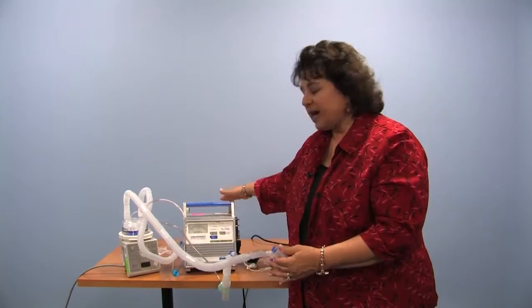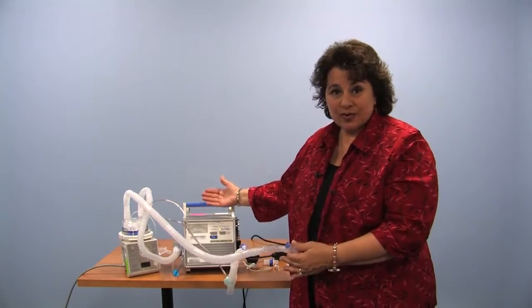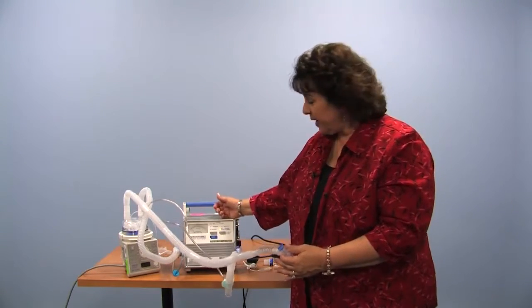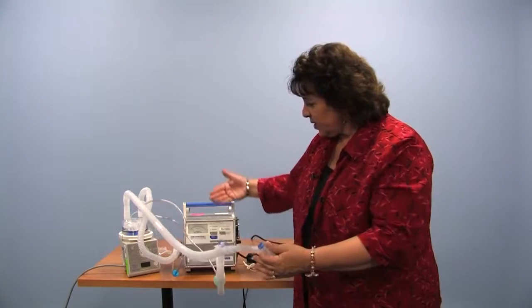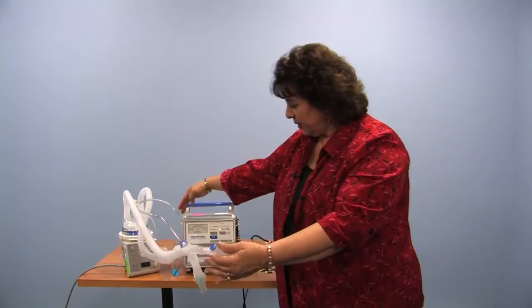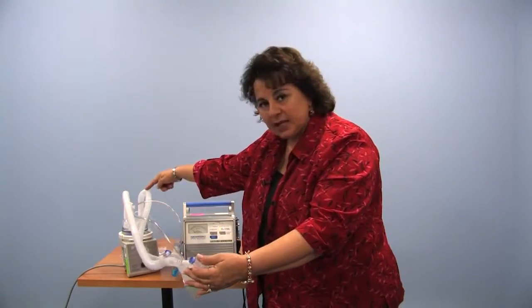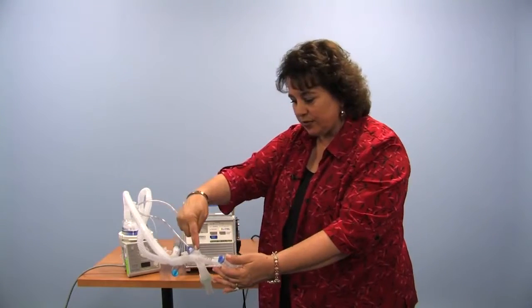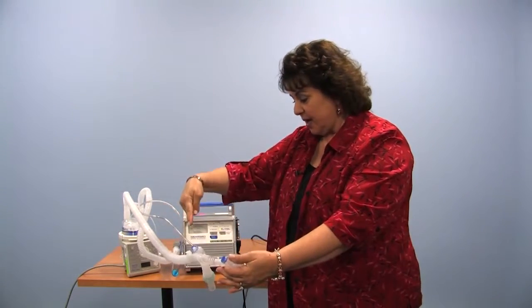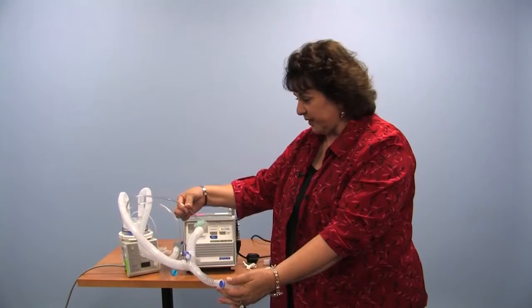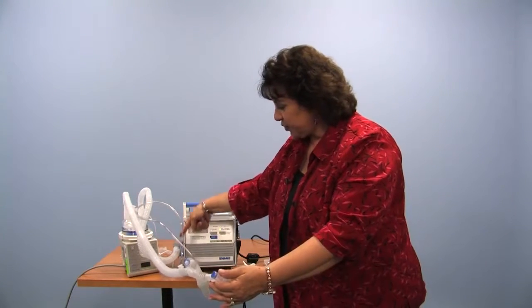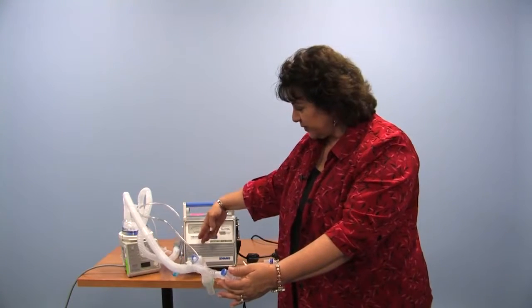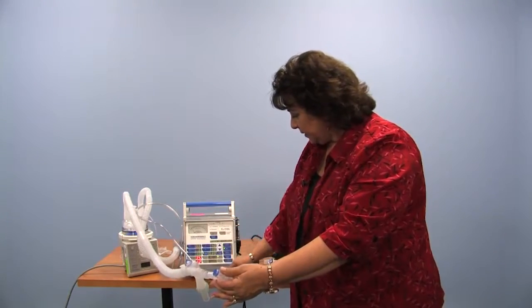It can be hung on the back of a wheelchair for those that are going out to school or out for social events. So this would be a configuration. The gas comes out, it gets heated and humidified, it goes out to the patient or child, and they exhale through the exhalation valve.